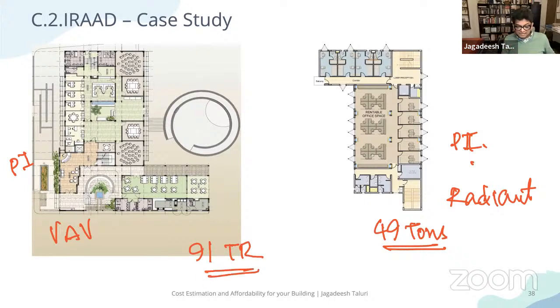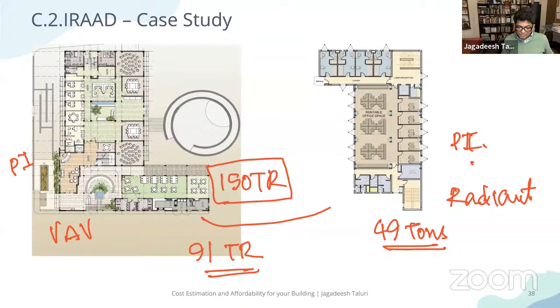But the installed chiller was 150 tons in phase one. They had actually bought a 150 ton chiller, and they were using the 150 ton chiller to run phase one alone. So when it came to phase two, they saw the peak loads, 91 plus 49. But what is the average operational load most of the year? Like 80% of the time, you're not peaking. That turned out to be 85 tons for both the buildings.